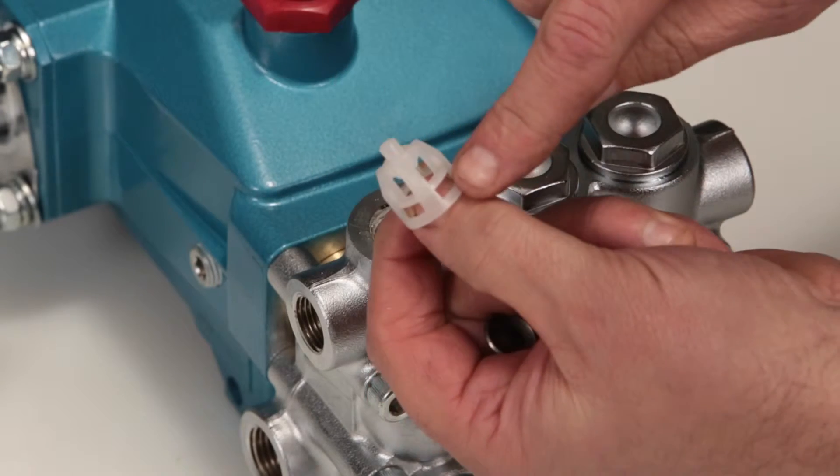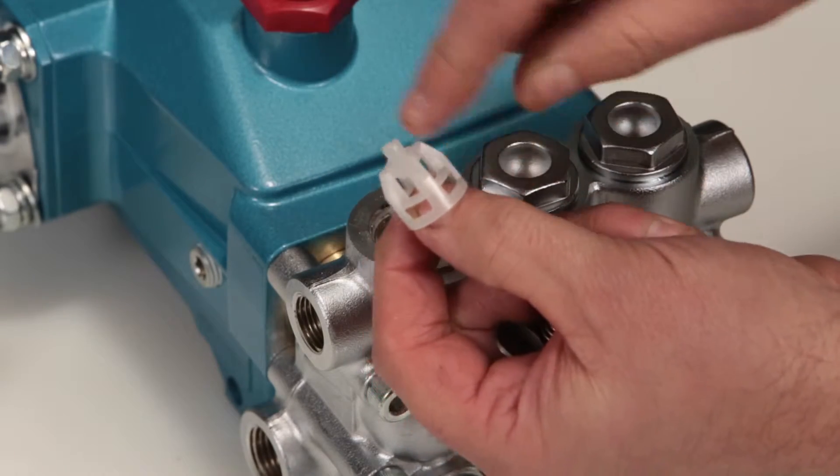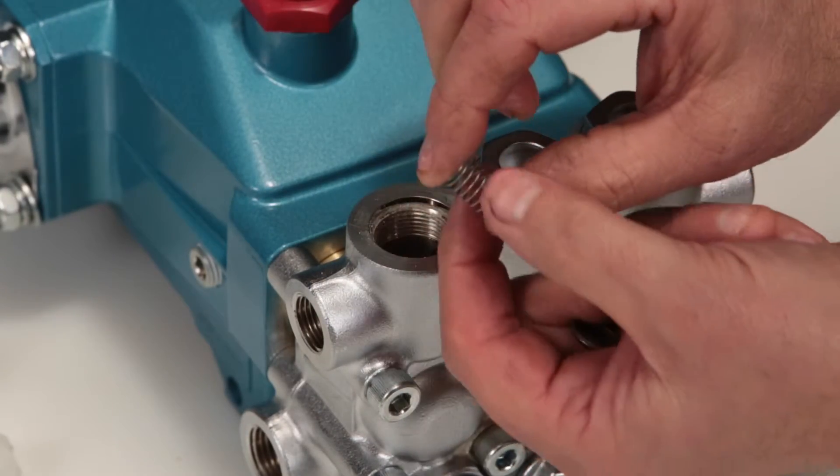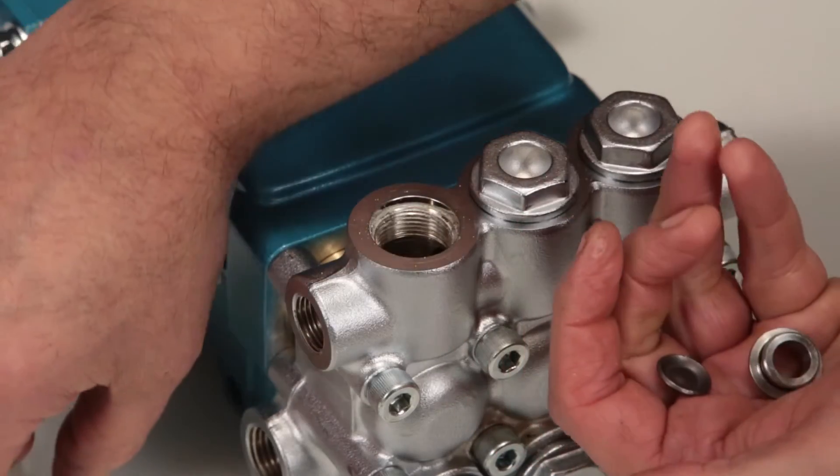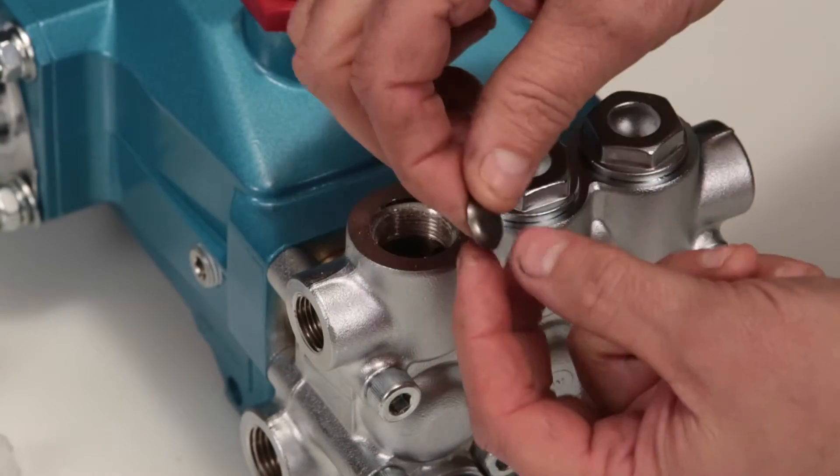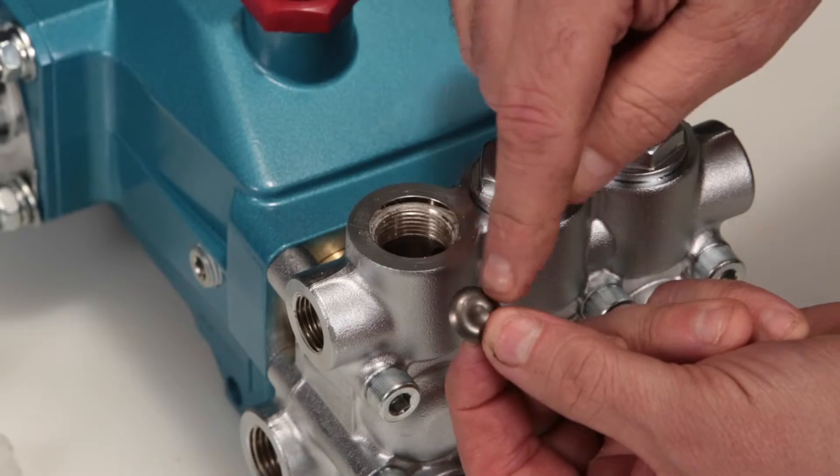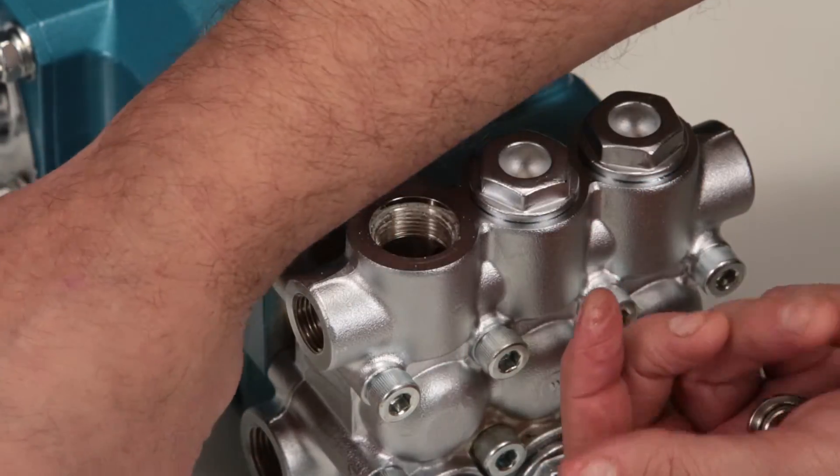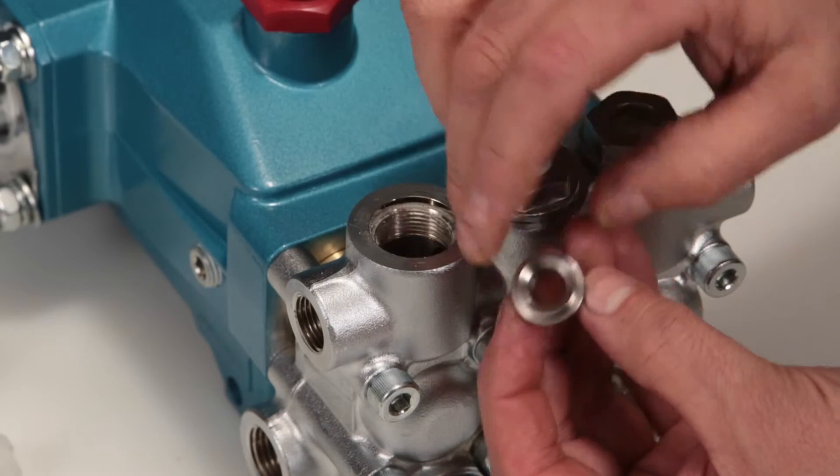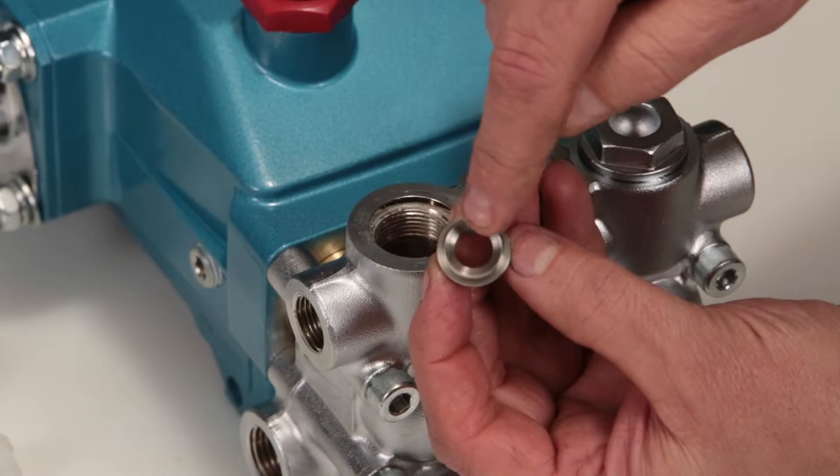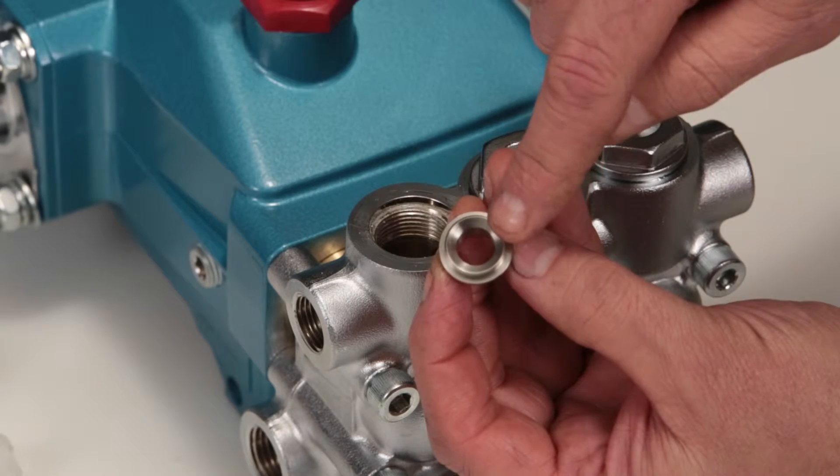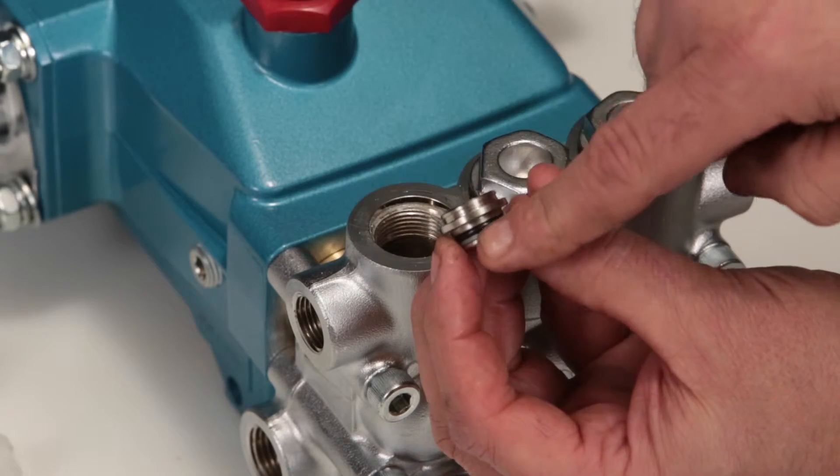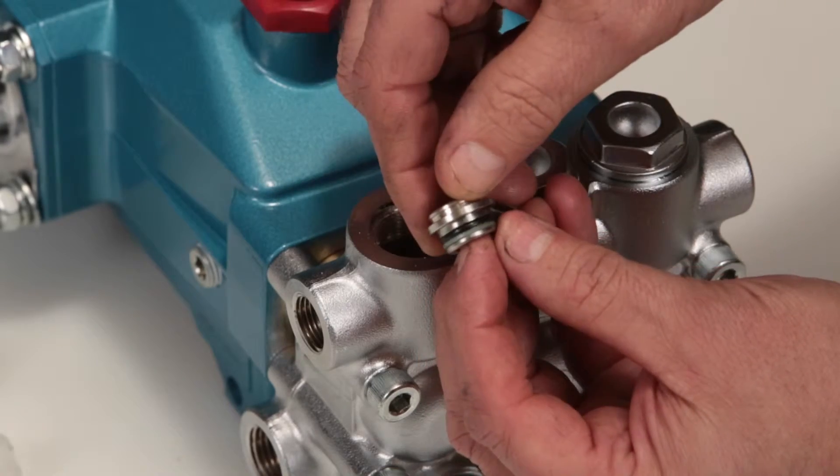Inspect spring retainer for cracks, excessive wear, or damage. Inspect spring for proper tension or any damage. Inspect tapered surface of the valve for wear, pitting, or damage. Inspect tapered surface of valve seat for wear, pitting, or damage. Pitting on the valve seat or valve is an indication of cavitation. Inspect valve seat O-rings and backup rings for cuts or nicks.